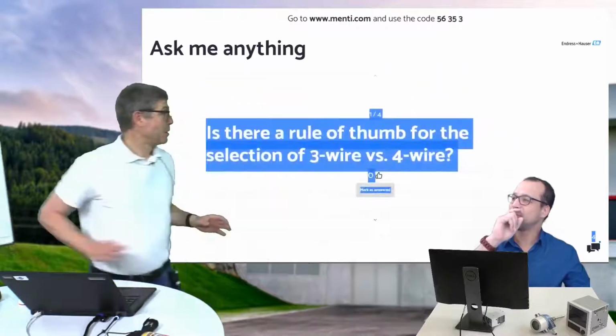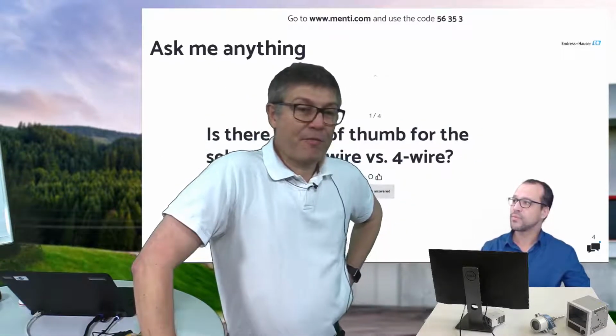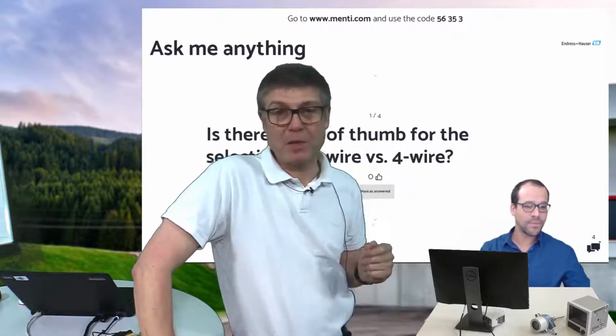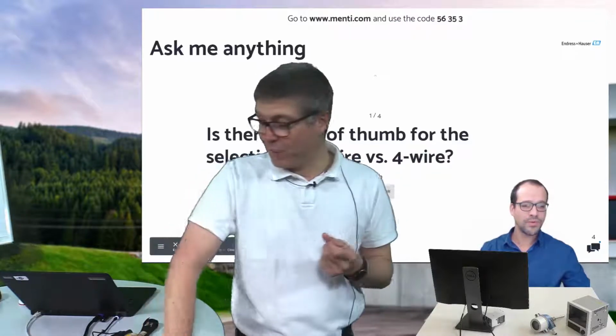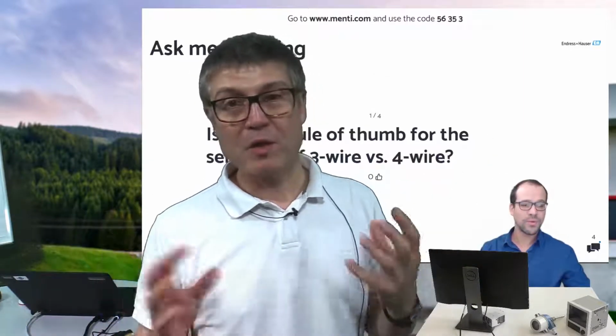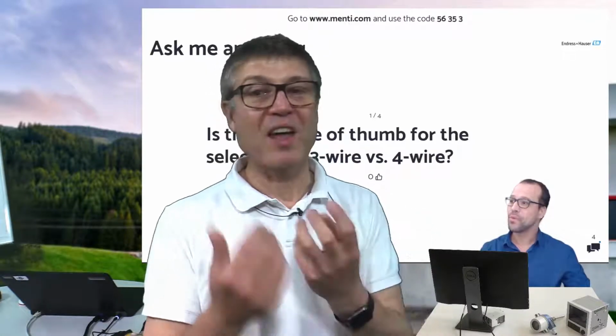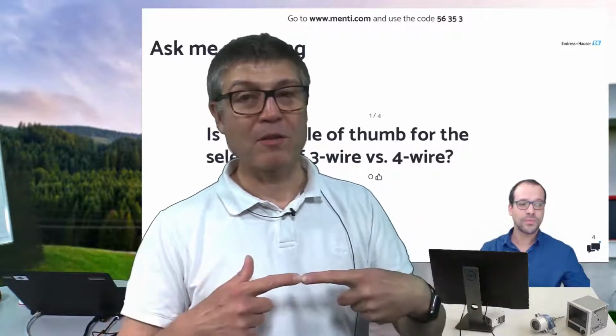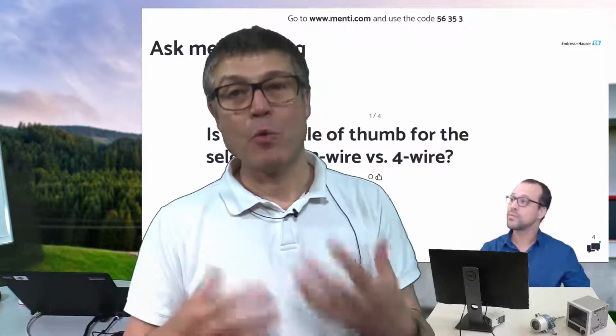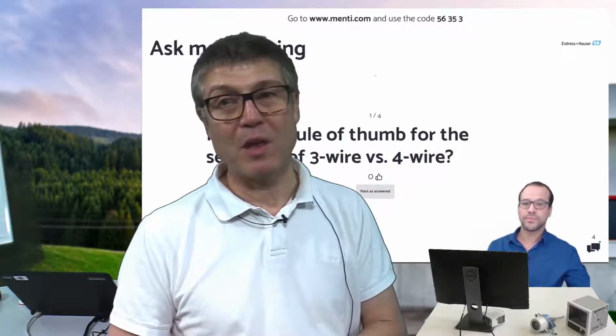No worries. Okay, then we have something else. Is there a rule of thumb for the selection of 3-wire versus 4-wire? I would say 3-wire is okay if you have connection cables from 10 to 20 meters or something. If you use mineral insulated cables, so if the measuring insert we supply is 1 meter long or whatever, we already recommend 4 wires, because the way to produce mineral insulated cables is very special and you cannot guarantee that all of these wires have the same resistance. For plastic cable, you can be quite sure that the resistance is very homogeneous around this cable. But for mineral insulated cables, if you exceed half a meter, I would recommend 4-wire.